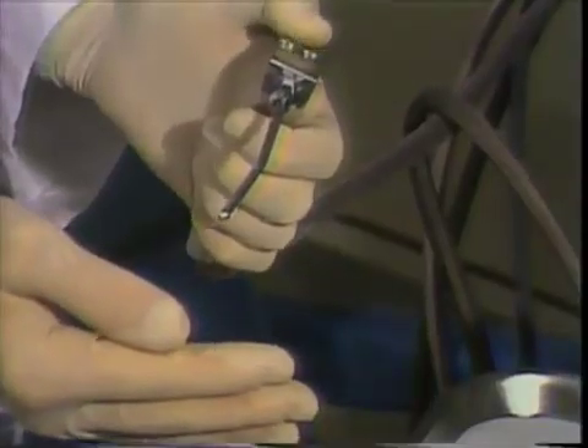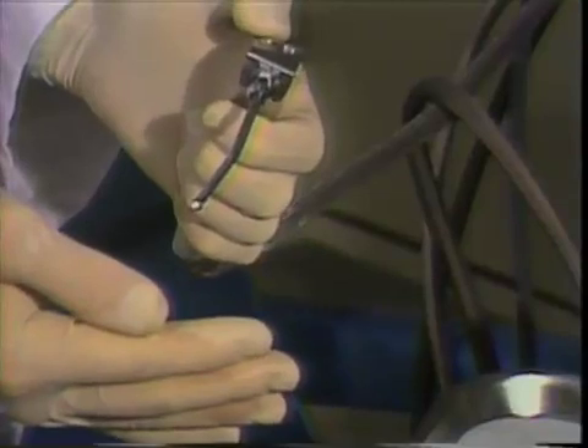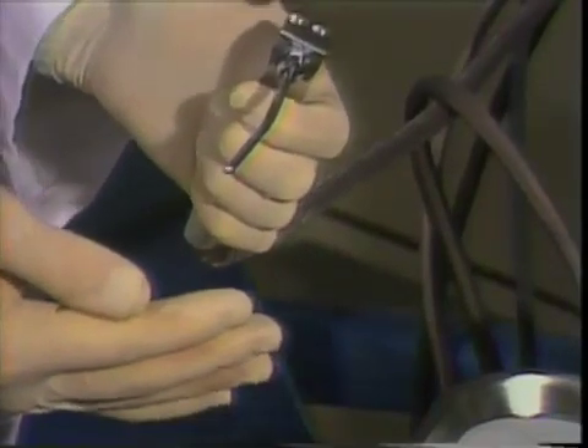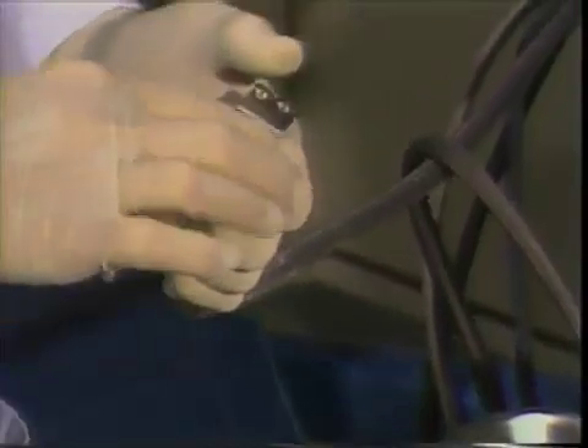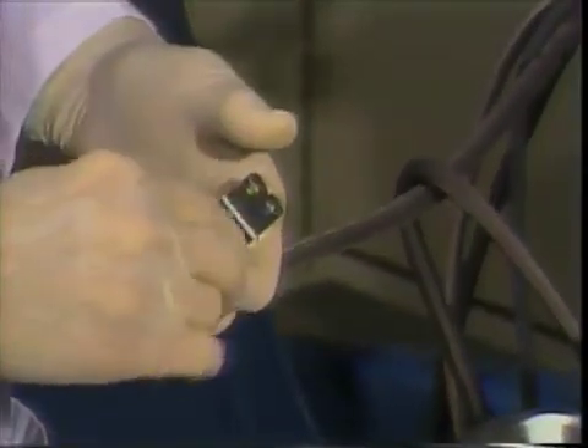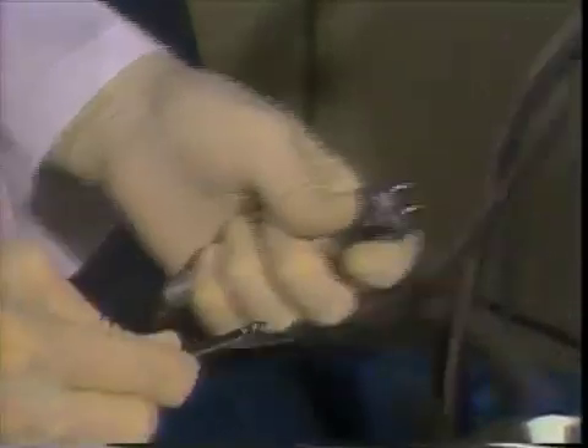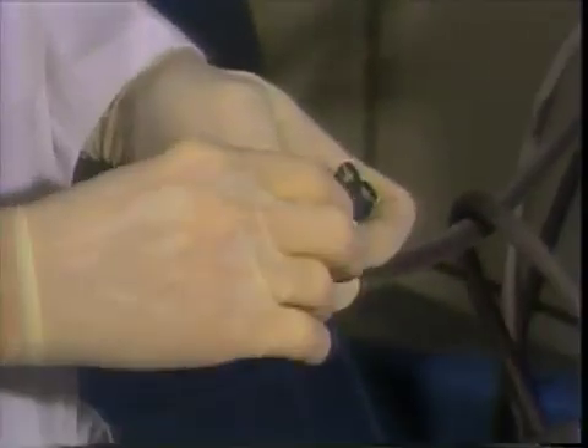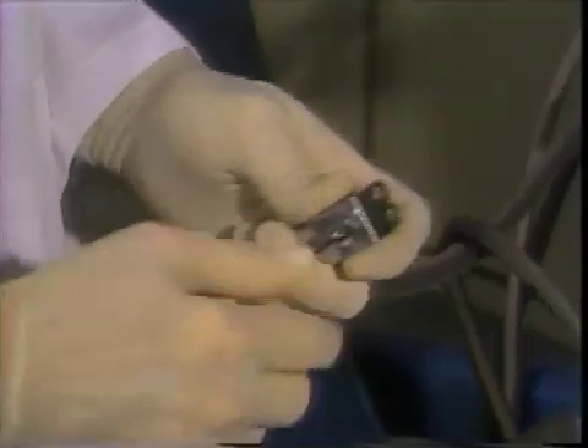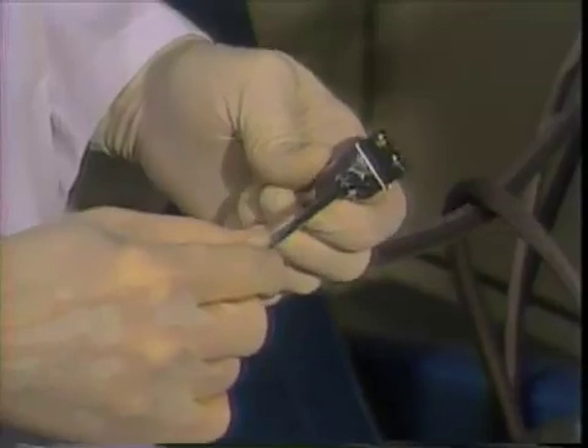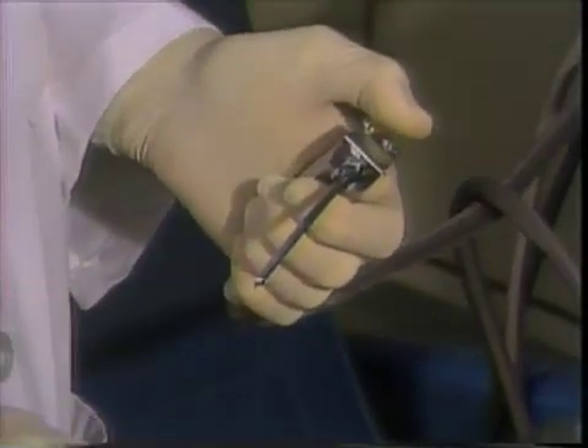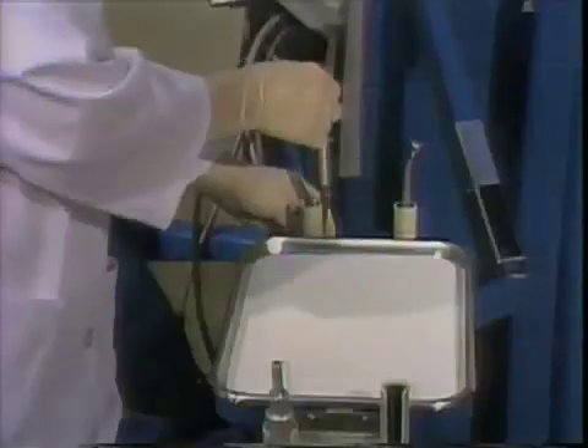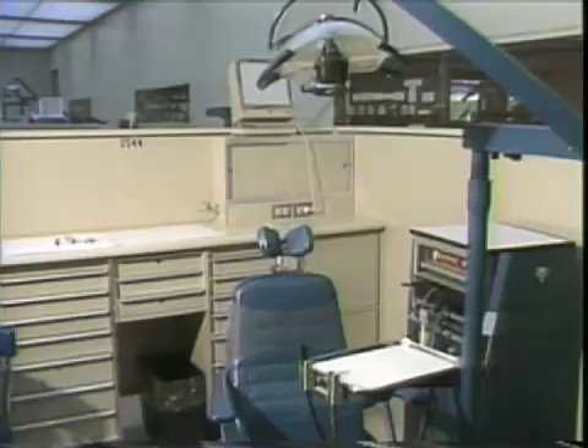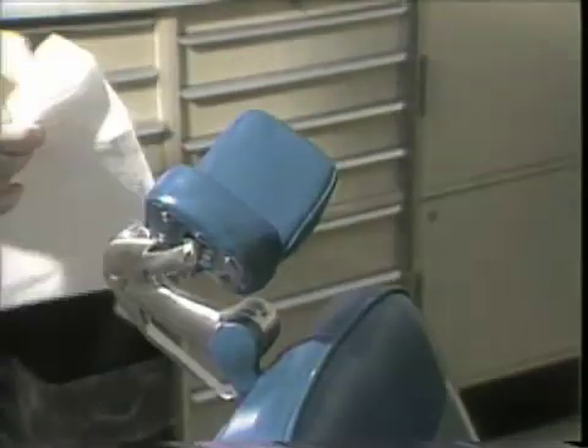Test the water, air-water combination, and air on your hand before using on a patient. If dripping from the syringe occurs, finger loosen the collar, reseat the tip, and finger tighten the collar. Test the three positions again on your hand. If dripping still occurs or the tip seems loose, call the equipment maintenance personnel. Then place the paper products out: the tray covers, the unit top cover, and countertop covers, and the headrest cover is placed.